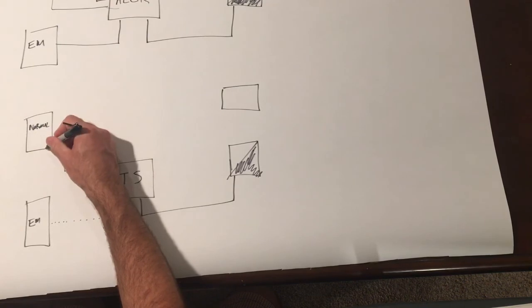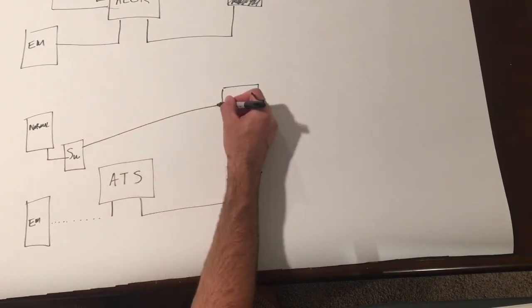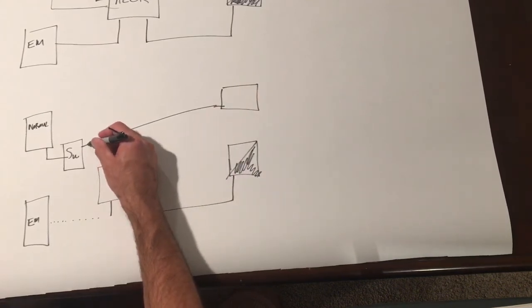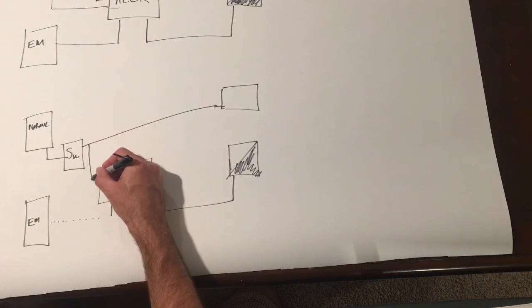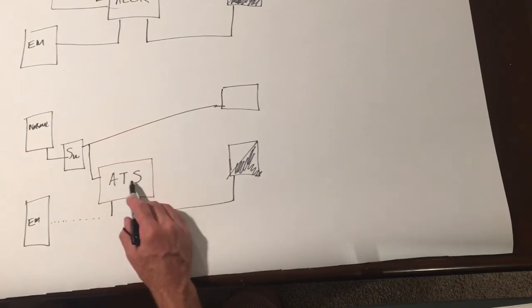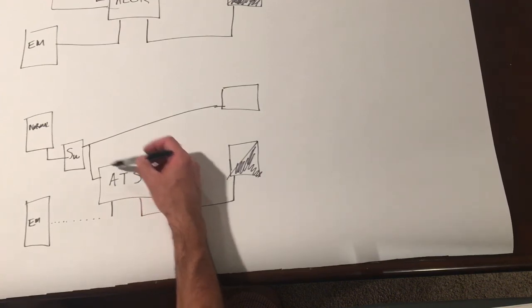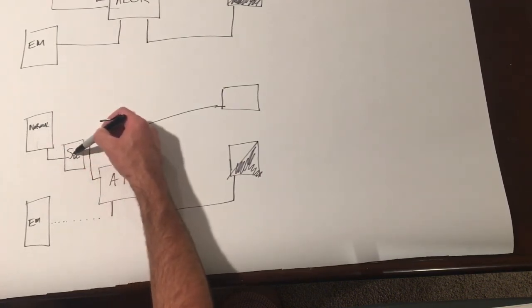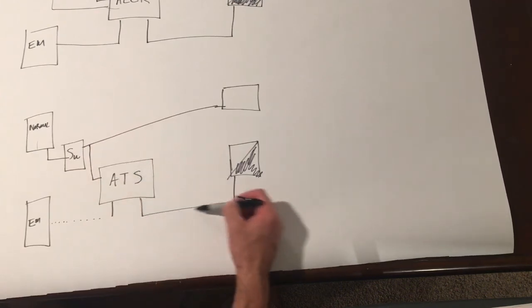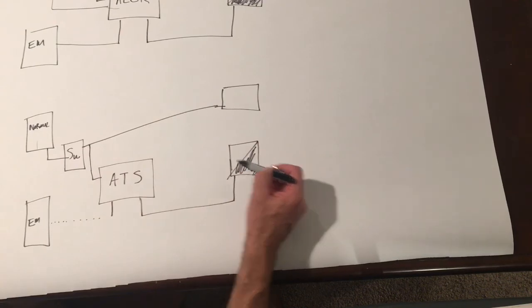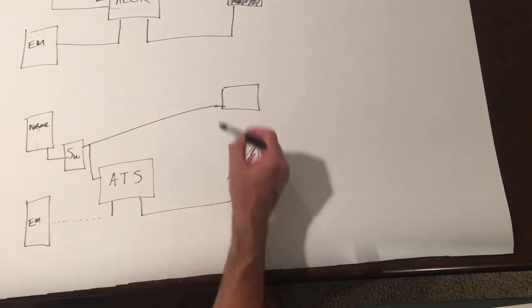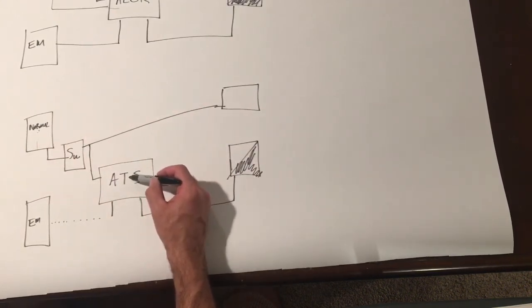Power comes out of here into the switch out to our normal fixture. And in this case, it also from the switch goes into the automatic transfer switch. What's different about this application is when you use an automatic transfer switch, normal power going through this switch, through the automatic transfer switch to this fixture. So this fixture is now getting powered by this panel. And so is this one. That panel is powering both of these through the automatic transfer switch.